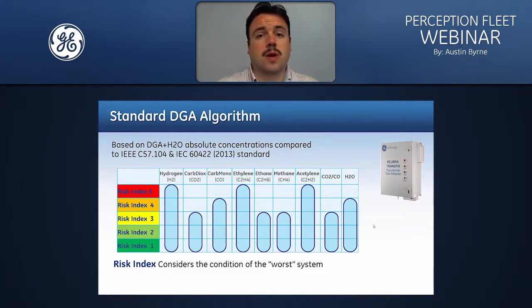And that means that no matter what the levels of carbon dioxide are within the transformer, it will never push that asset into anything higher than a risk index of 3. Whereas if there are high levels of hydrogen, or even acetylene, for example, in the transformer, that transformer can reach a risk index of 5.